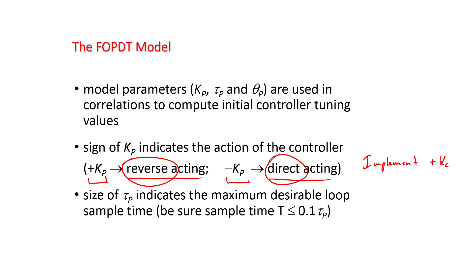The sampling frequency is also important for tau_p. We need at least 10 samples in every time constant of time. So if you have a time constant of 2 seconds, you need a sampling frequency of at least 0.2 seconds — the sampling time needs to be that fast or faster.